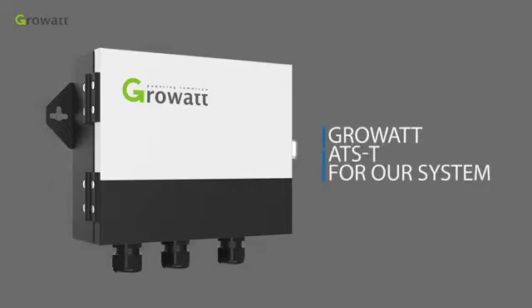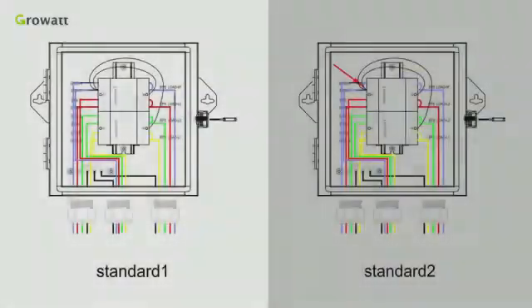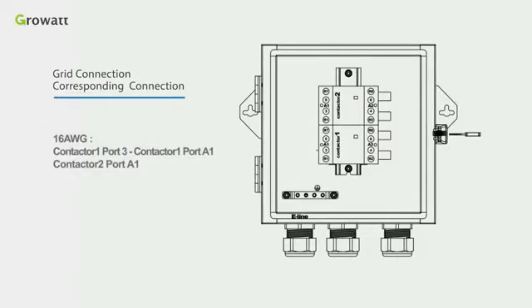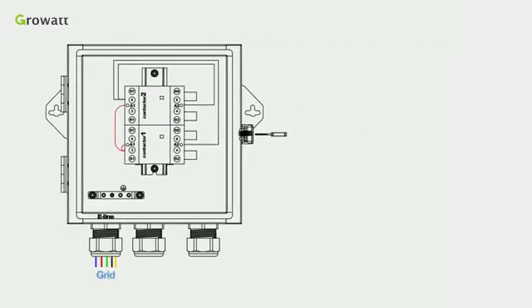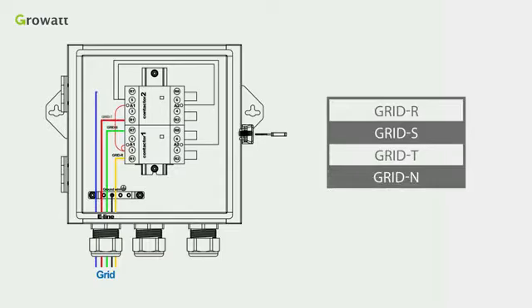If the customer requires the backup power function, Growatt provides the optional ATS-T for the system. Follow the diagram to connect the ATS-T. Standard 1 is for general use and Standard 2 is for markets like Australia where the neutral line cannot be switched. Use 16 AWG cable to connect contactor 1 port 3 to contactor 1 port A1 and contactor 2 port A1. Use another 16 AWG cable to connect contactor 2 port 5 to contactor 1 port A2 and contactor 2 port A2. Then connect 10 AWG cable of grid R, grid S, grid T, and grid N into the corresponding ports as illustrated, and lock the ground cable on the copper bar.